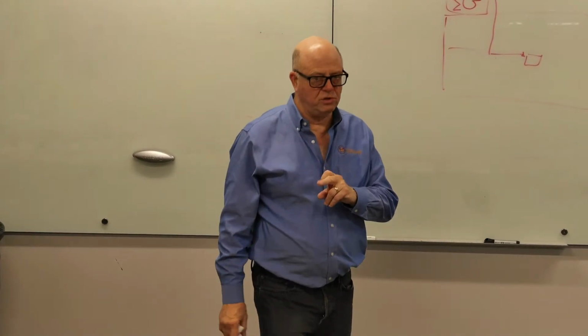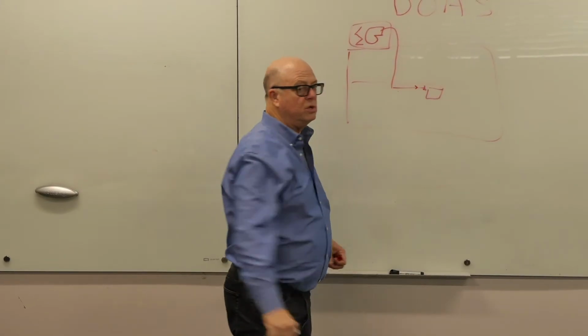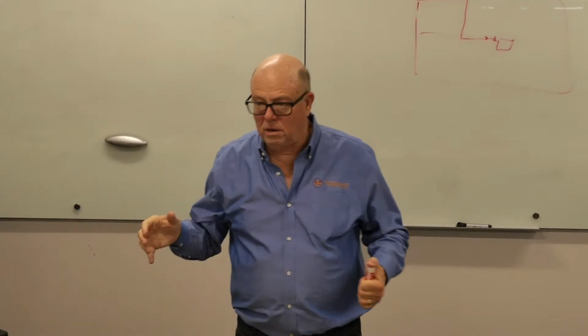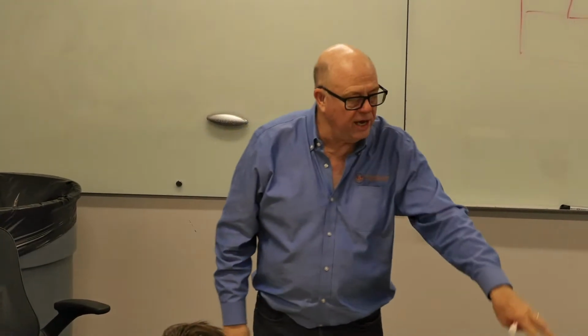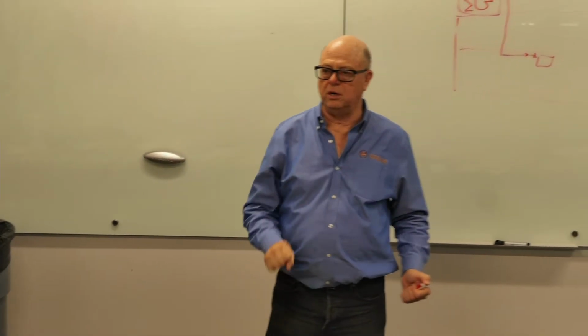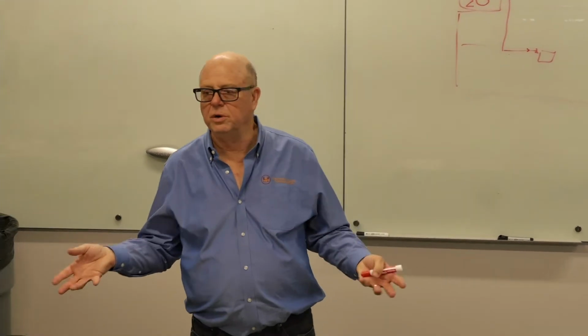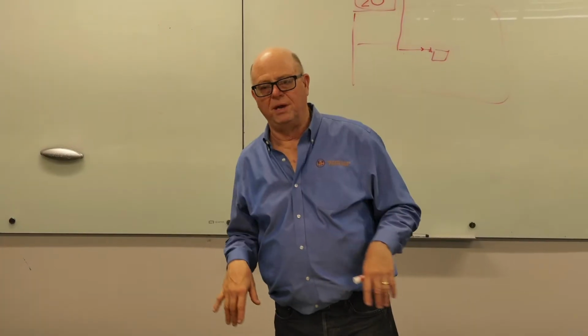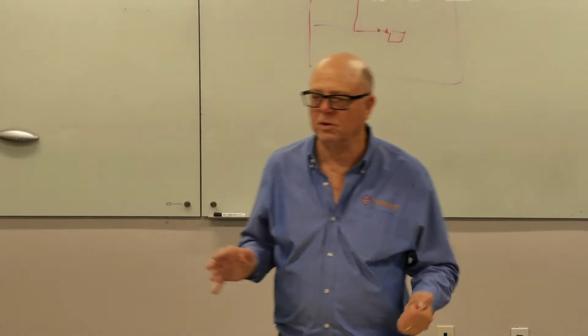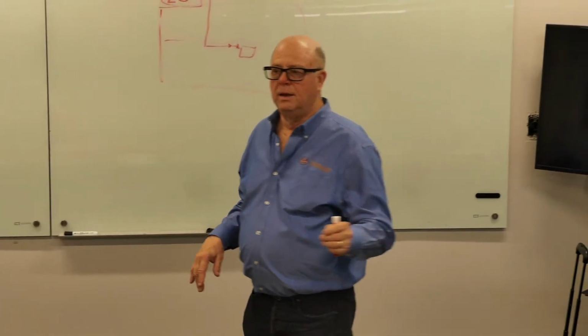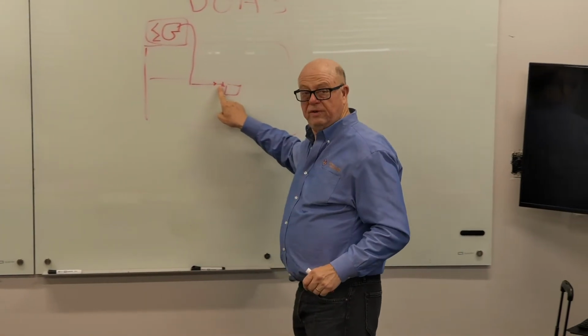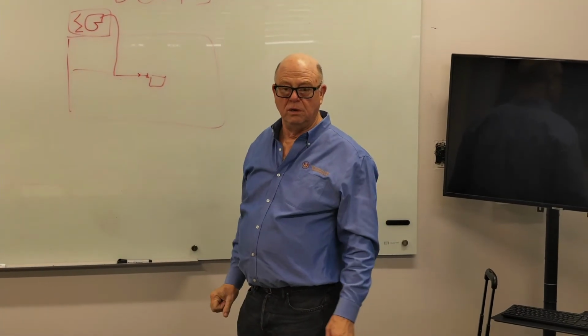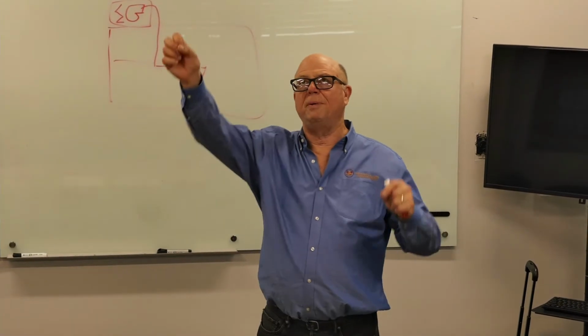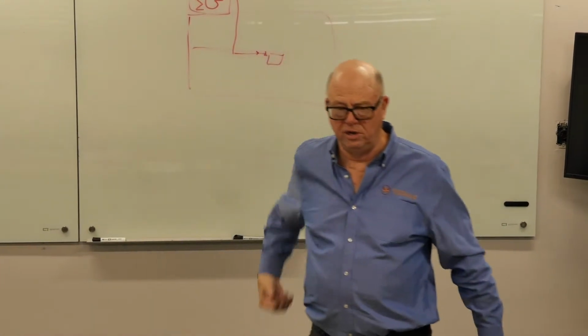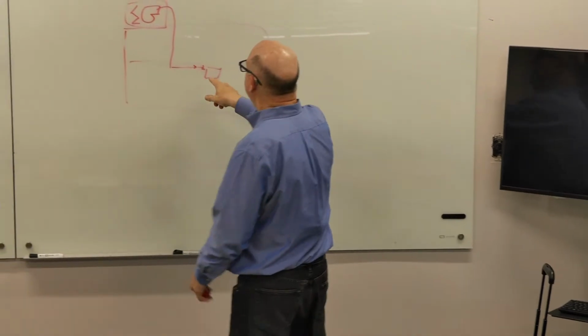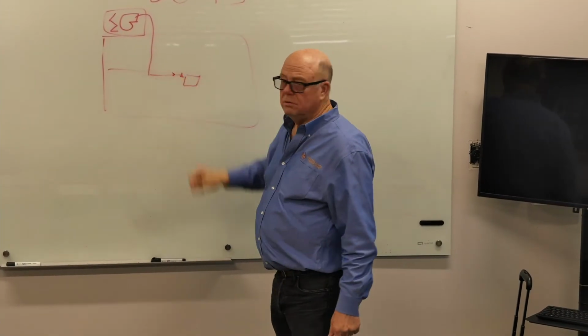And that was supposed to be balanced, because you were supposed to be able to make sure that you had the code required engineer design CFM for every fan coil that was outside air, because there was a ventilation air requirement. Depending on the time, it might have been 5, 10, or 15% were the typical numbers, depending on how far back you go. So we're putting our outside ventilation air in at the back of the fan coil unit, and at some point along the way the code said, no, just dropping it off at the back end isn't good enough, you have to hard duct it into the back of the unit. Okay, so we'll do that. And we got to balance it.